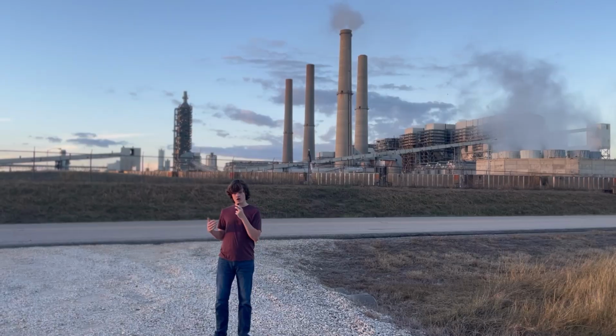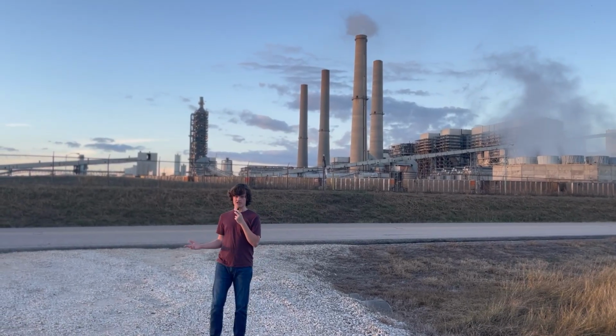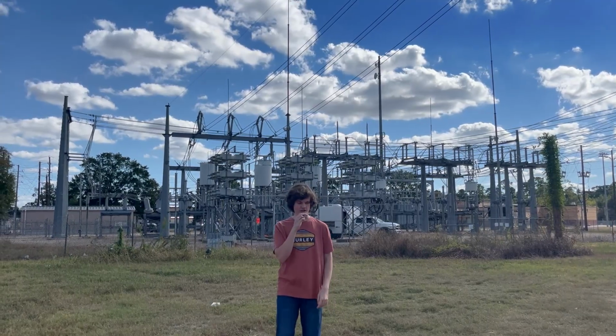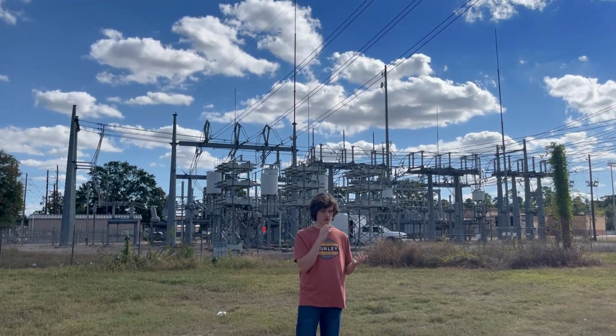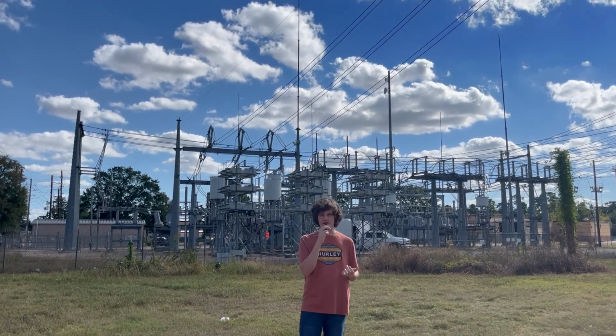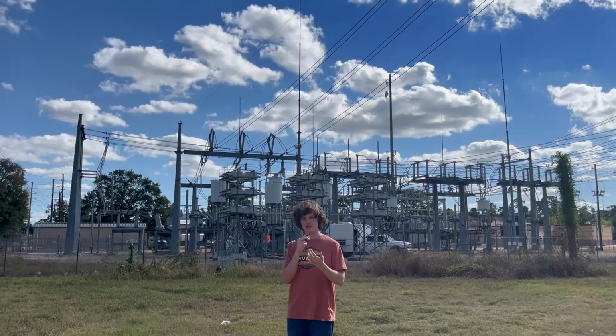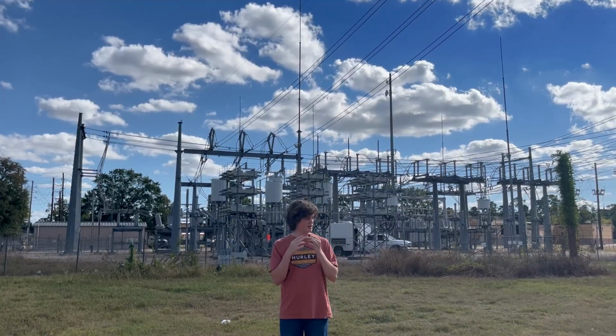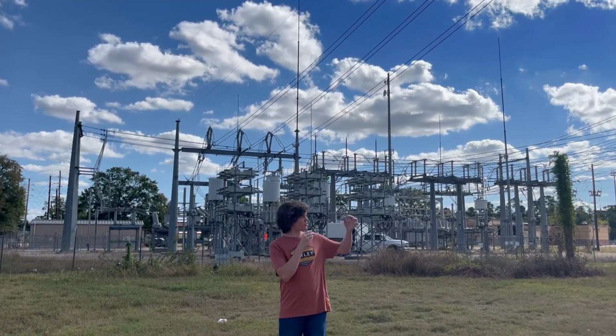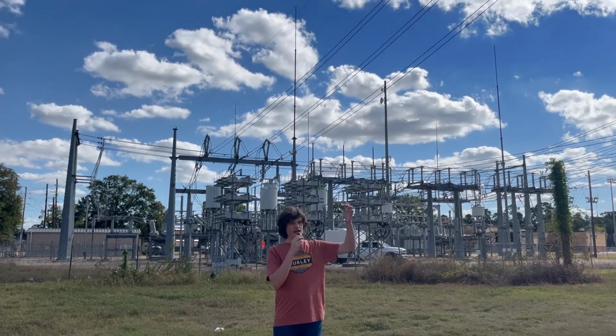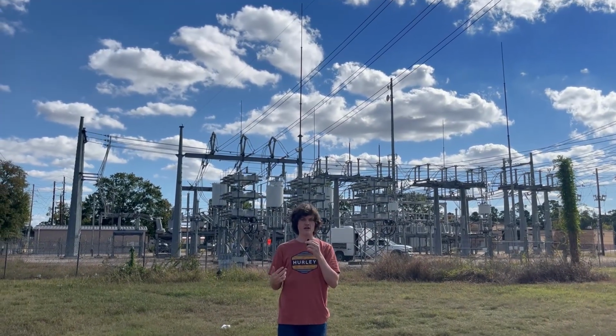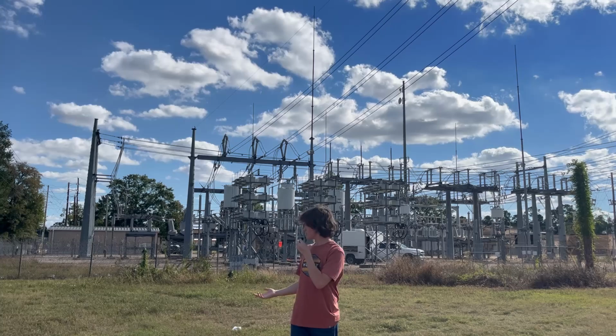But once we pass it over these lines, where exactly does it go? I'm here at a power substation, which has two primary roles on our power grid. The first is much the same as the banks of transformers we saw at the power station, except that instead of stepping up the voltage, it takes voltage from these high voltage lines and steps it down an order of magnitude to between 10 and 20,000 volts.